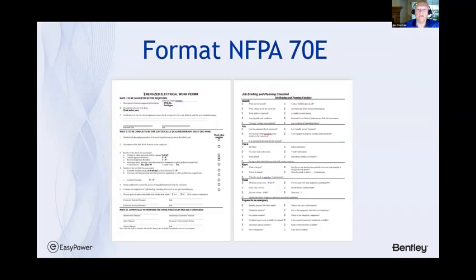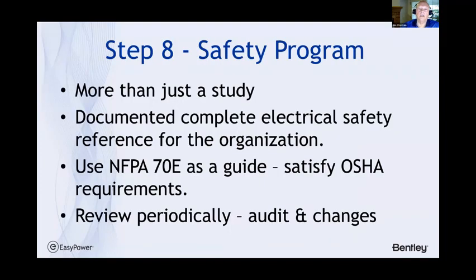There are examples in NFPA 70E, and software like EasyPower can produce these automatically utilizing the results of the safety assessment. And this would be where any enhanced mitigation steps like quicker tripping units would be invoked for the work in process. An arc flash risk assessment, as well as some of these other steps, is just part of an overall safety program, and it's more than just the study. And so it needs to be documented as a complete electrical safety reference for the organization, and policies should be encouraged such that management is as serious about the application as the qualified workers.